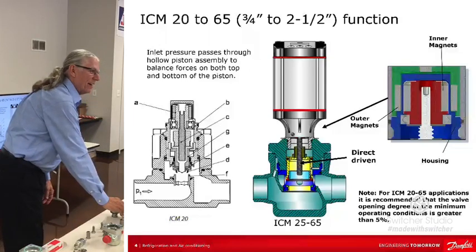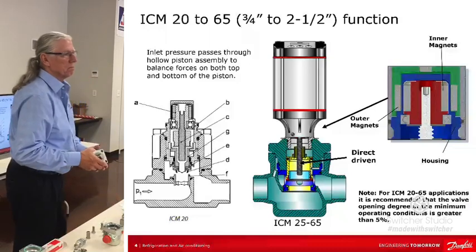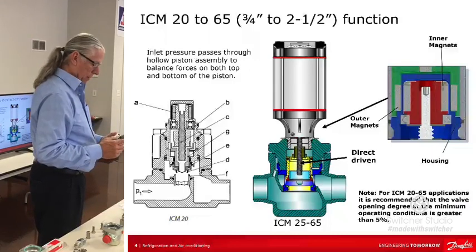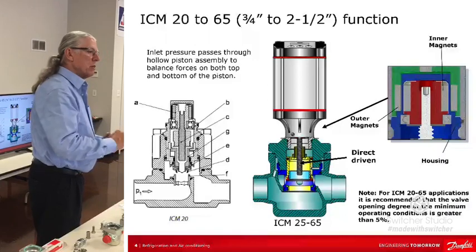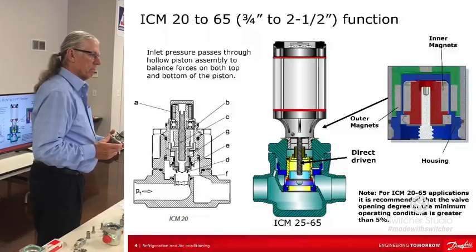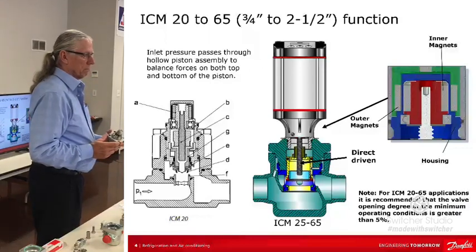So how do you know the valve with the valve? I mean, you got the magnet in here. How do you physically verify that this thing is? It's actually that one doesn't have an encoder in it, so it doesn't know. Yeah, it does. That one does? Yeah, it's a 600A. Okay. So it's standard now. We don't sell it without the encoder. It knows it from the current and the resistance. But on that, it knows how that's fit, and it doesn't know how that's fit, right? Because what happens if somebody goes and takes a manual thing and puts it halfway, puts it on there?